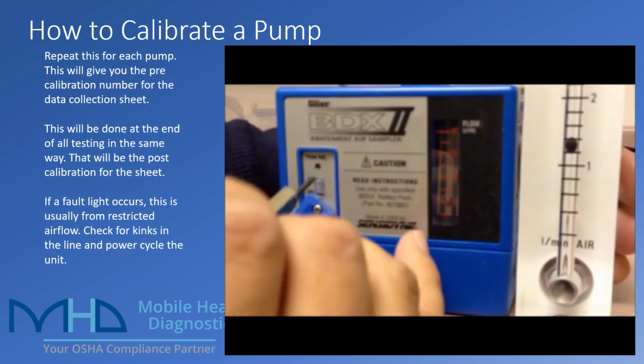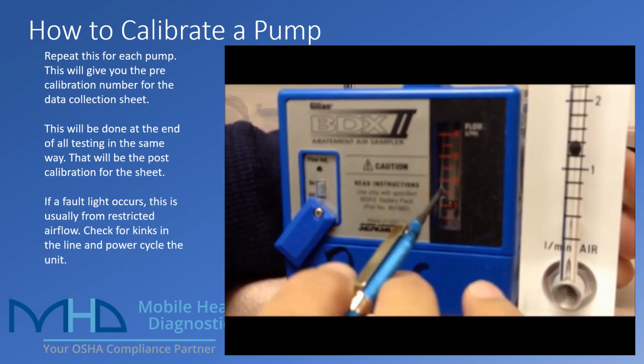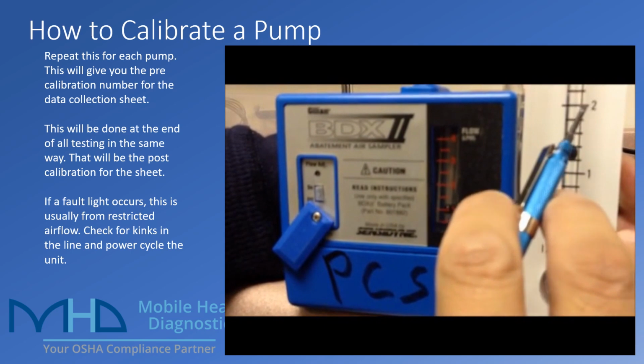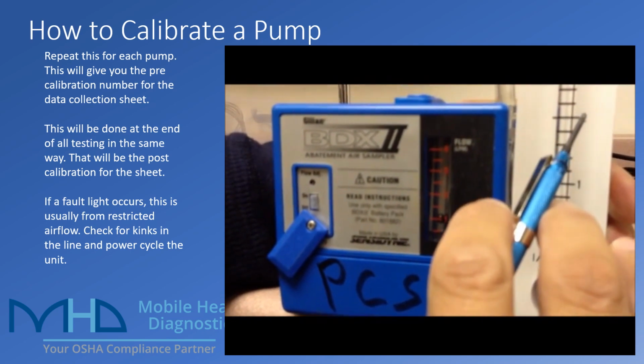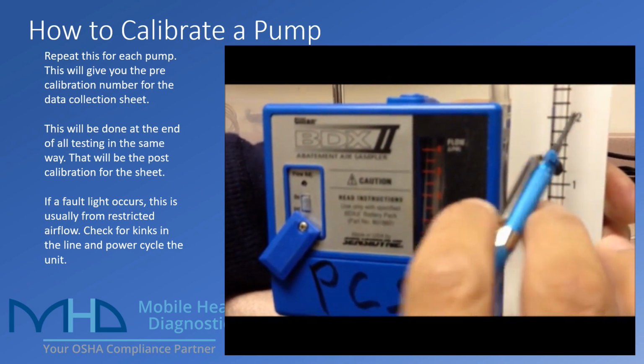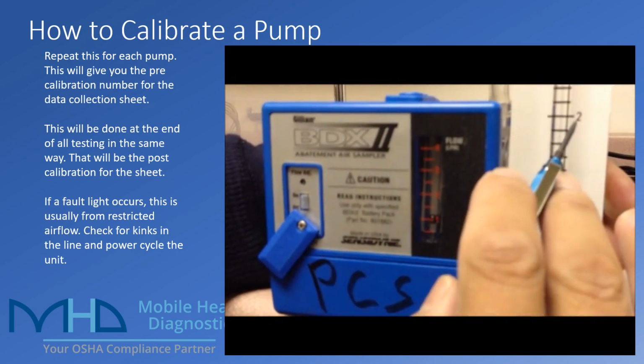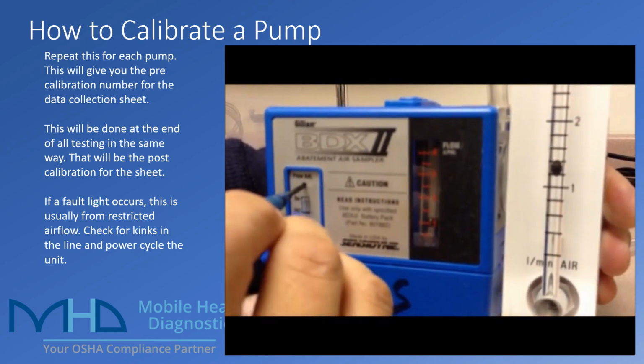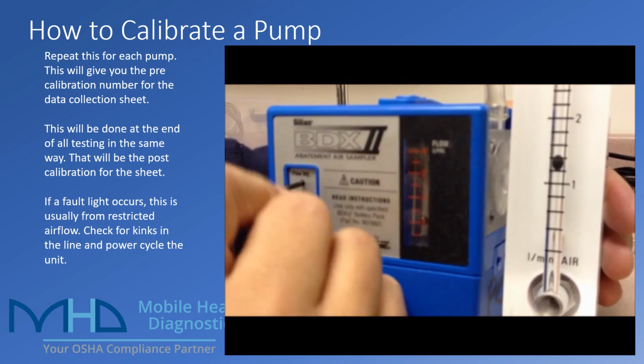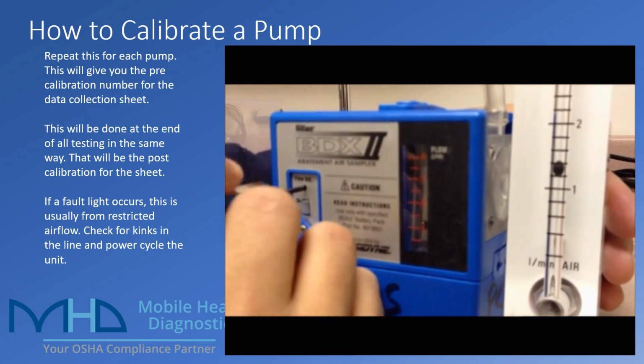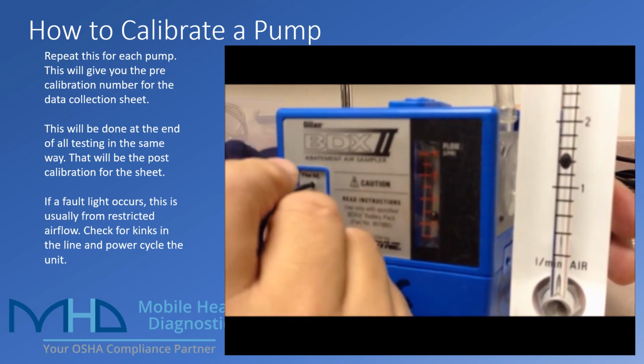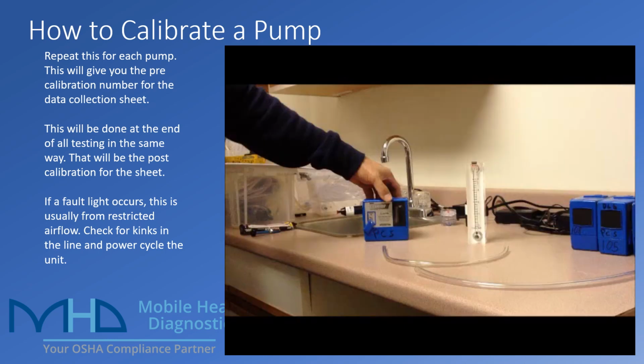And the nice thing being here is that this is almost an instantaneous adjustment. So the calibration goes quite quickly. And again, the equator line of that ball bearing is sitting right at 2. And you're going to repeat that for each one of your pumps, matching it up with the intended flow rate that was shown on the pump inventory sheet. So if it's 2, 2.5, 1, it should also be noted that at very low values, it can be very difficult to tell if the pump is on. They are quite quiet when they're at low flow rates.